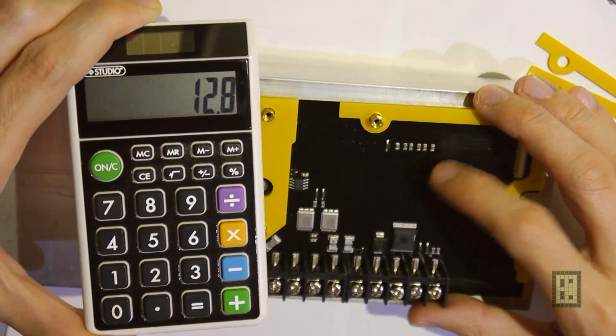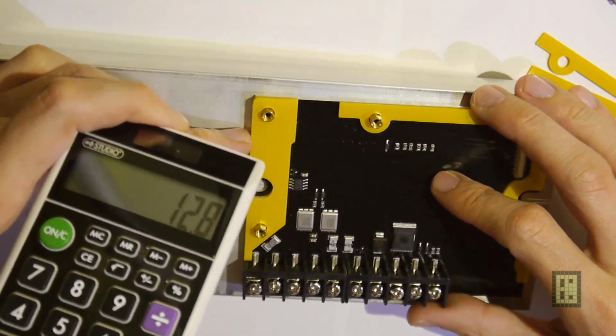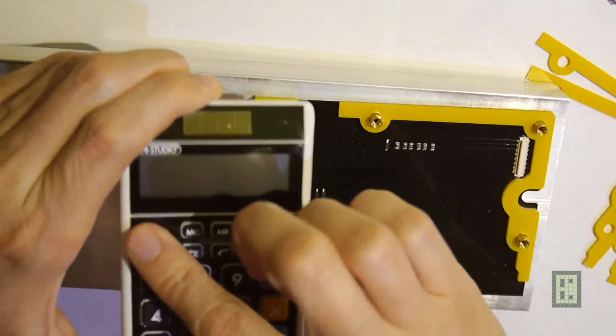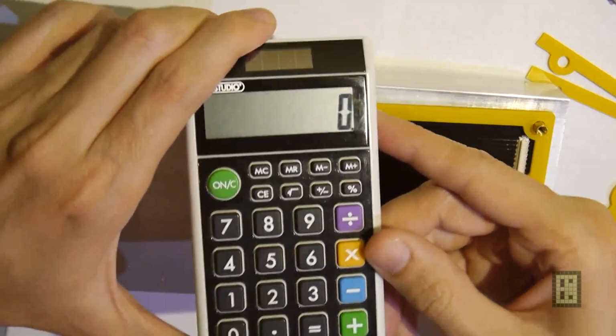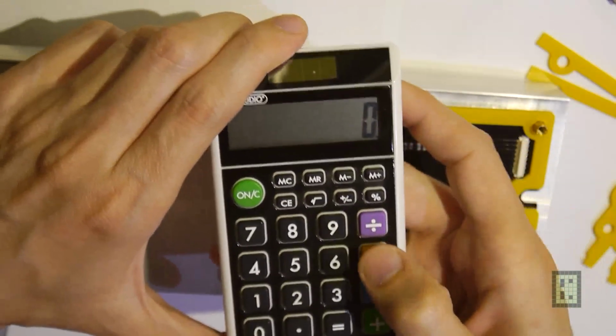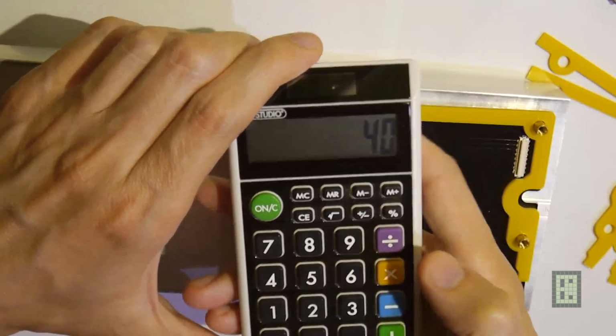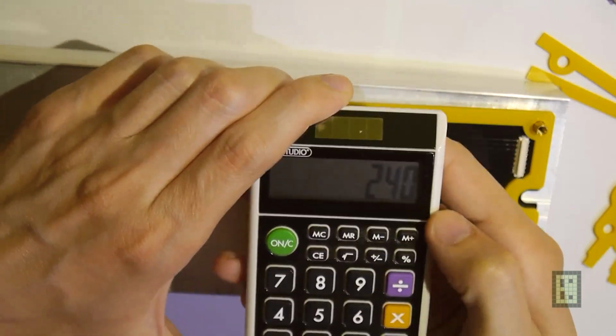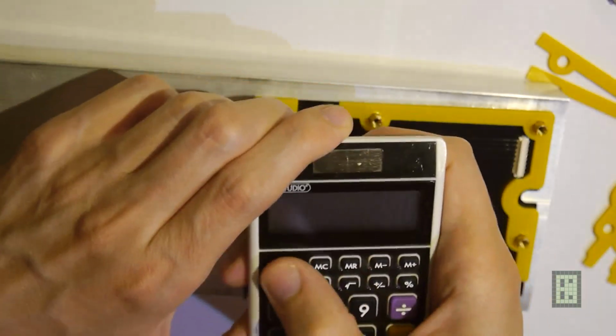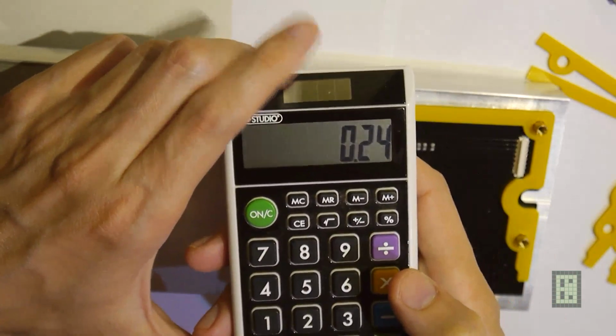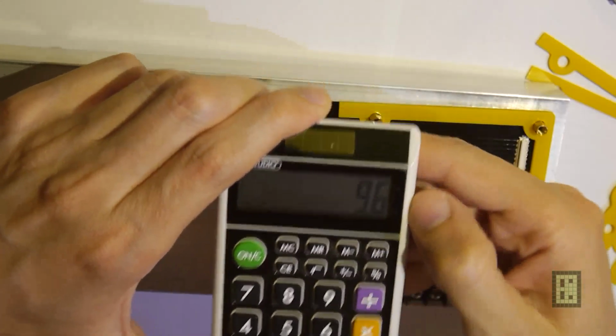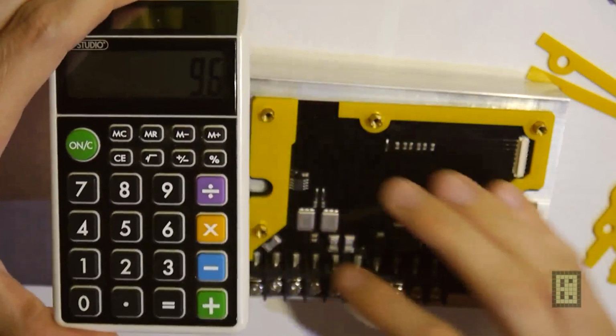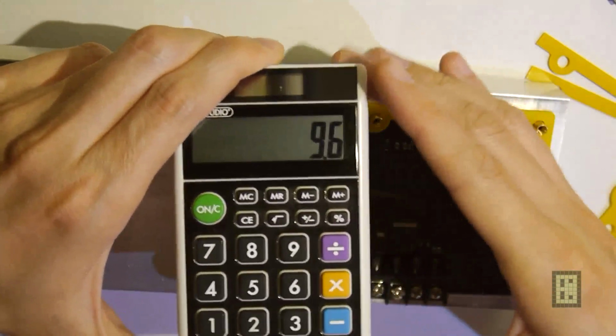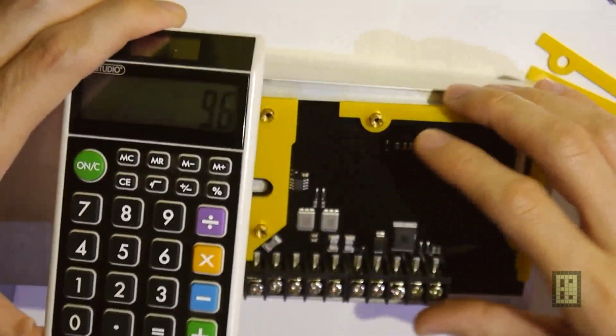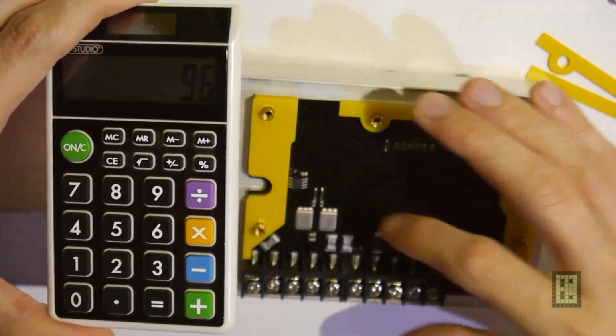So this will exceed what this can do without any additional heat sinking. Let's calculate the maximum heat dissipation on the charging part: 40 amps maximum multiplied by 6 milliohms gives 240 millivolts, so 0.24 volts multiplied by 40 is 9.6 watts dissipated on the charging part, so around 22 watts in total if you use this with 40 amp charging and 80 amp discharging simultaneously and continuously.